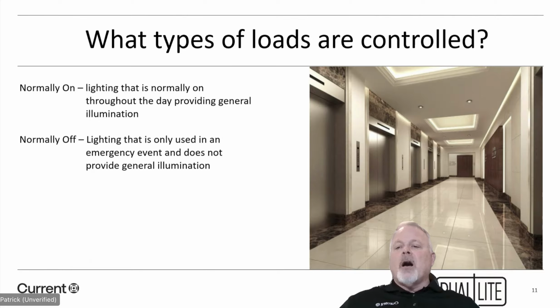We either have normally on or normally off. An example of normally on would be a luminaire or luminaires that we're using that are wired from the inverter to that specific luminaire. Normally off would be if we are wiring in, for example, an emergency lighting fixture. Bug eyes would be a good example of that. They are not normally on, they are normally off. So that's why they fall under that category.